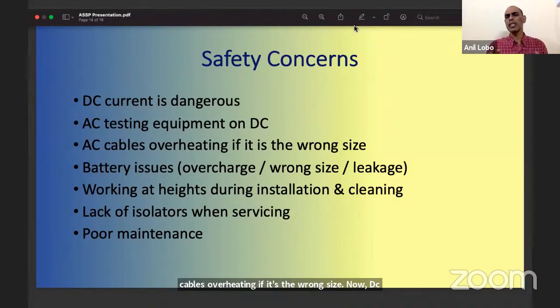DC cables and designing of DC cables is an engineering calculation. You have to do a proper DC voltage and current calculation - the length of the cable, the size of the cable, the load that is being used. If you don't do it properly and just guesstimate using the same numbers you'd expect for AC, you're in deep trouble, because the moment you fire up the system, you're going to damage the insulation first. When the insulation cracks, the cables will touch each other and short out. Once it shorts out, it'll overheat and can cause a catastrophic fire.